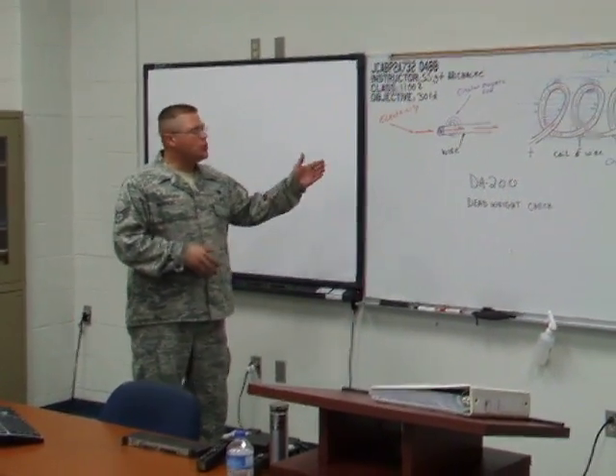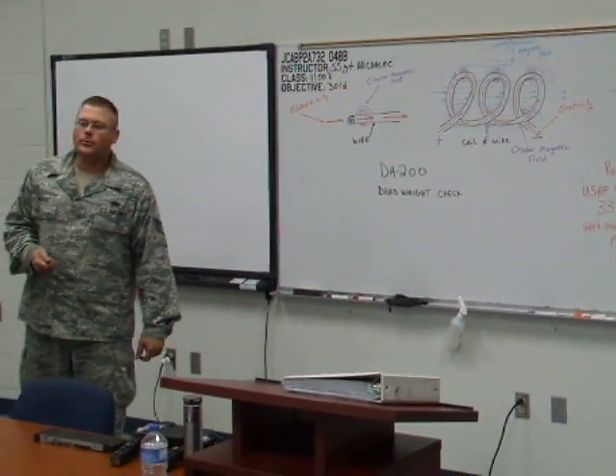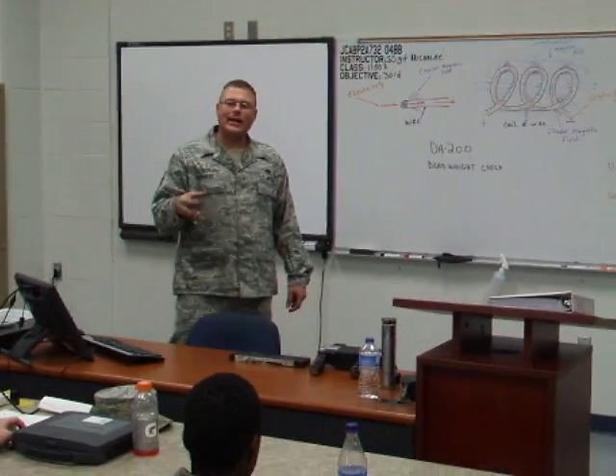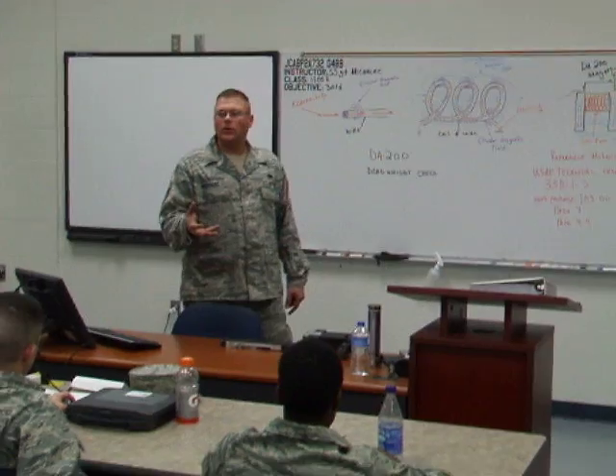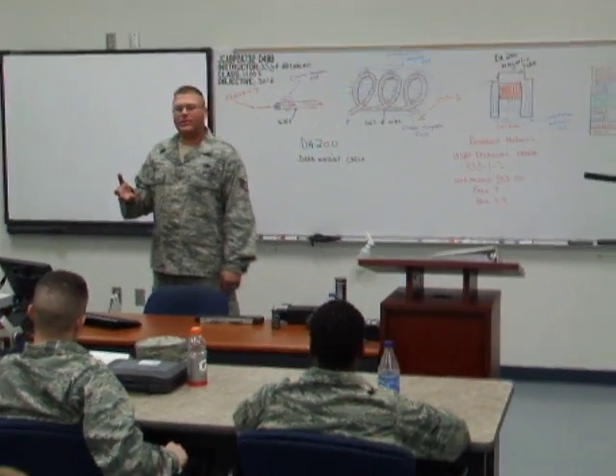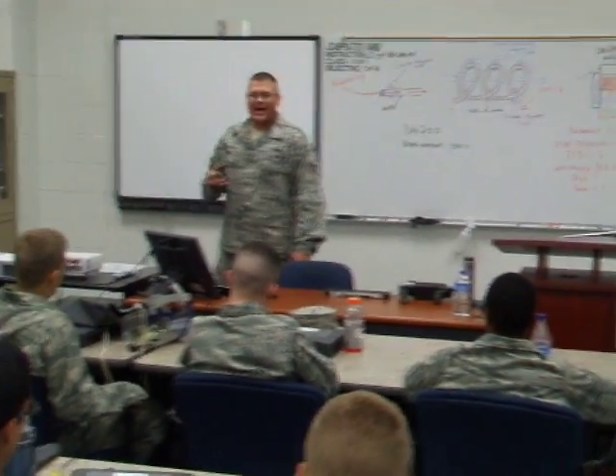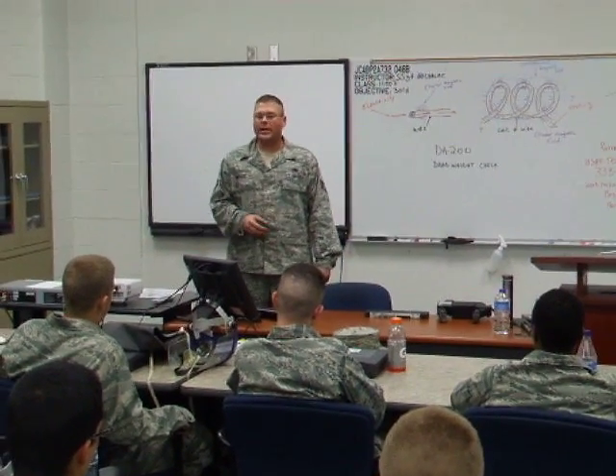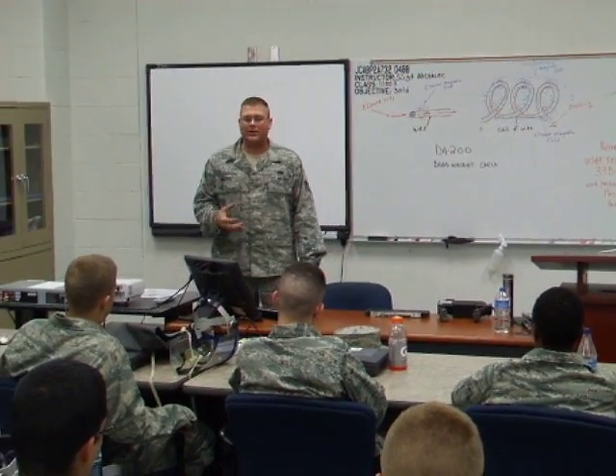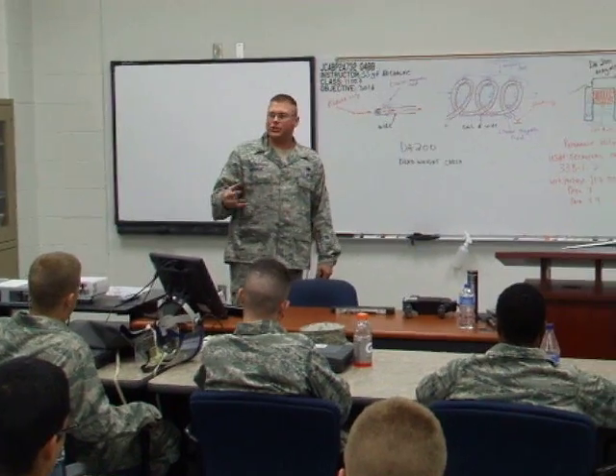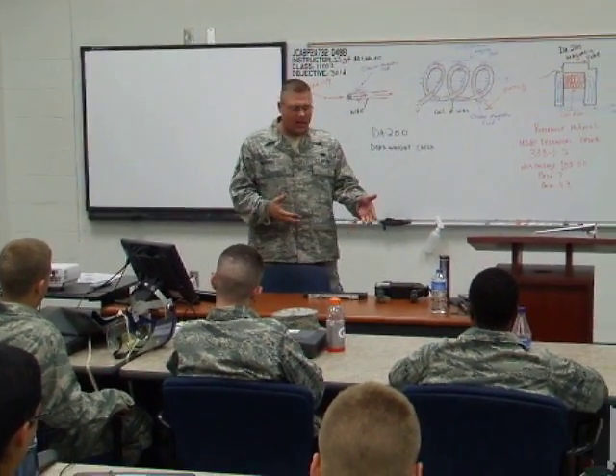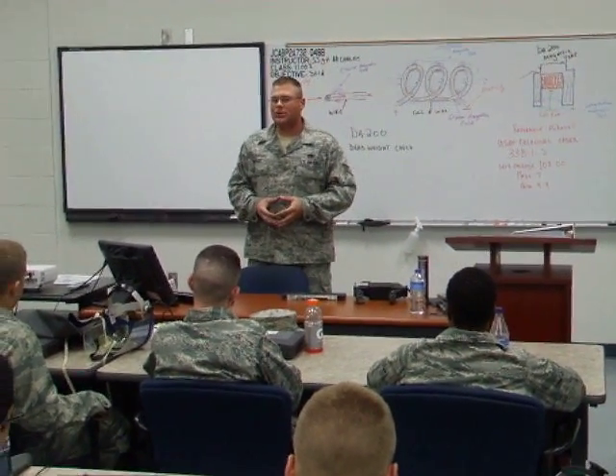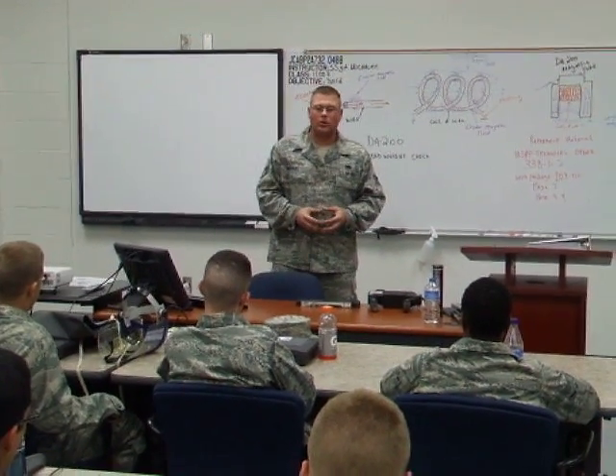To go over a little bit of how this device works, when you put electricity through a wire, it creates what's called a circular magnetic field in and around that wire. Now, you take that same wire and you coil it. While the circular magnetic fields are still there, they're going to concentrate themselves in the axis of that coil, therefore creating what is called a longitudinal magnetic field. It is this longitudinal magnetic field that makes this device possible to work for doing non-destructive inspection in both the military and the civilian world.